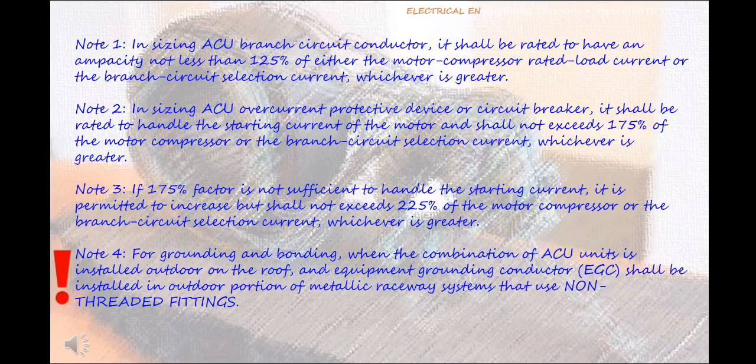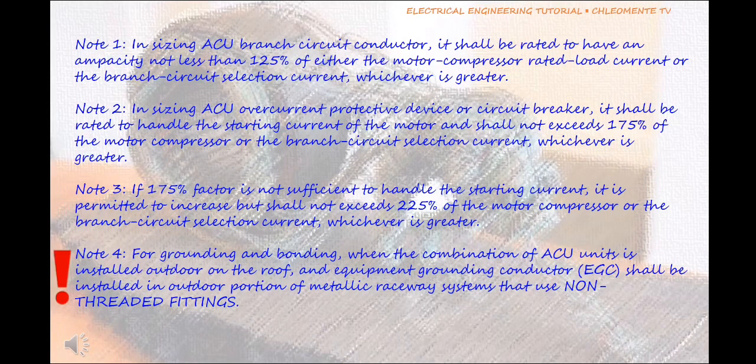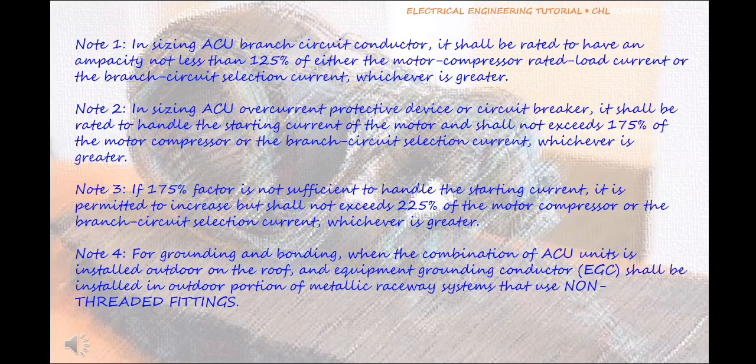Note 3: If 175% factor is not sufficient to handle the starting current, it is permitted to increase but shall not exceed 225% of the motor compressor or the branch circuit selection current, whichever is greater. Note 4: For grounding and bonding, when the combination of ACU units is installed outdoor on the roof and equipment grounding conductor (EGC) shall be installed in outdoor portion of metallic raceway system that use non-threaded fittings.